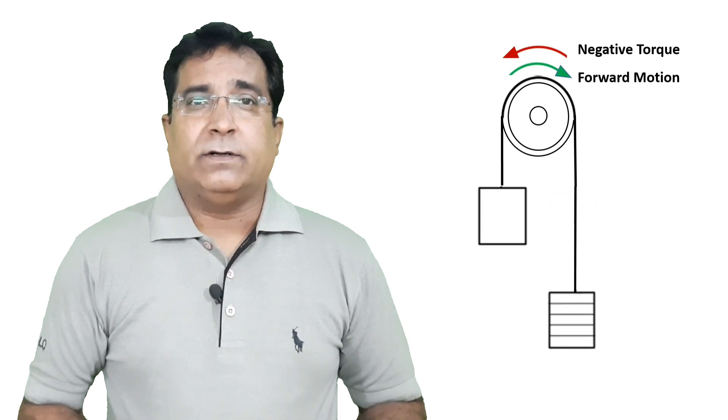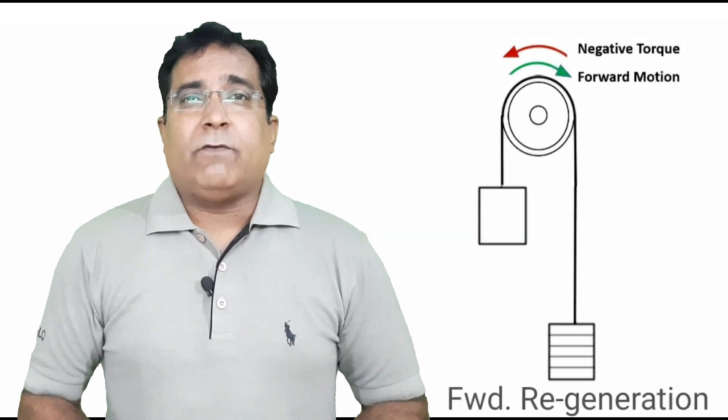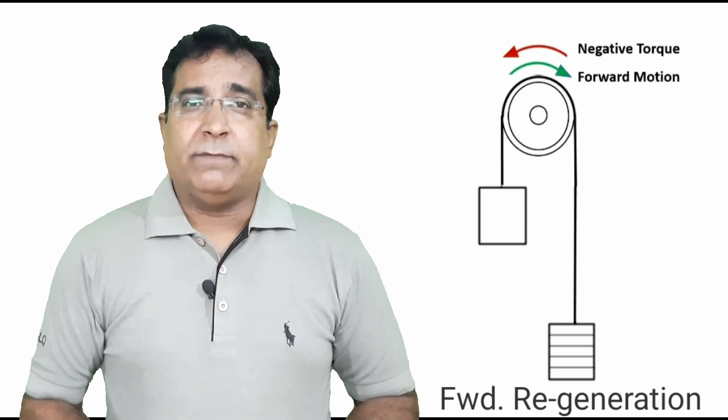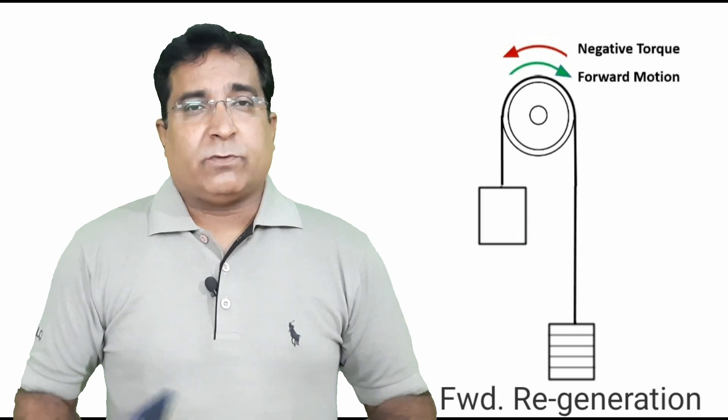Here the empty car is called up from bottom. Again the motor needs to be run in forward direction. But the weight of empty car is less than weight of counterweight. So the gravity will pull the counterweight downward causing the motor to rotate in forward direction with effect of gravity on counterweight. But to limit the speed of empty car under safe limit, motor now will generate a negative torque against gravity and limits the up speed of empty car. This puts the motor into regeneration mode.